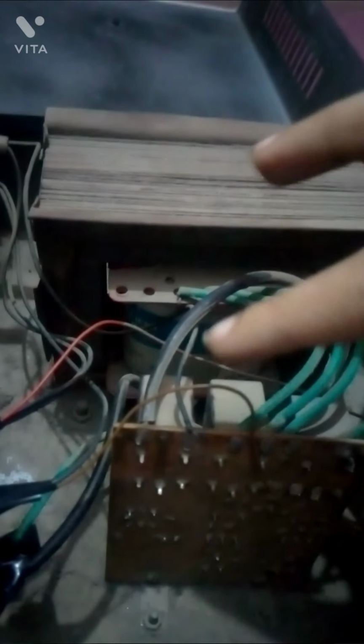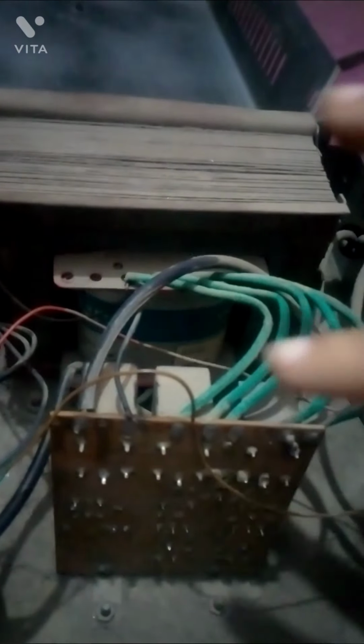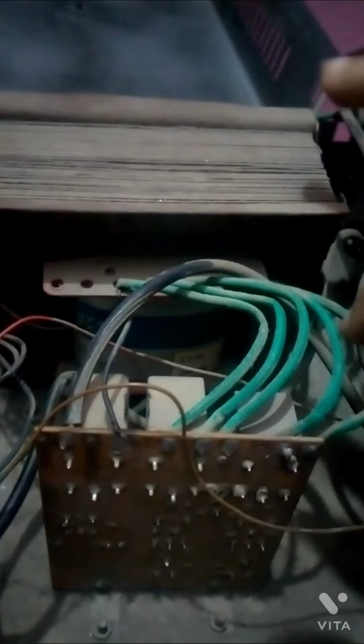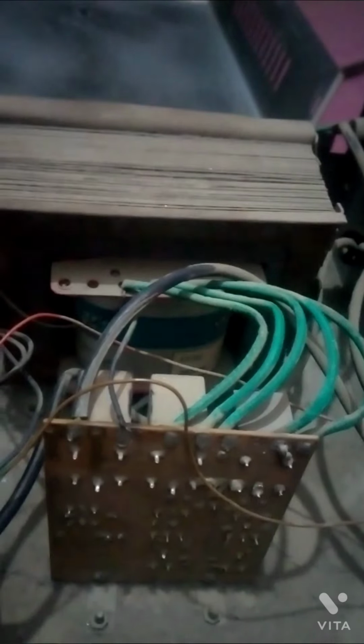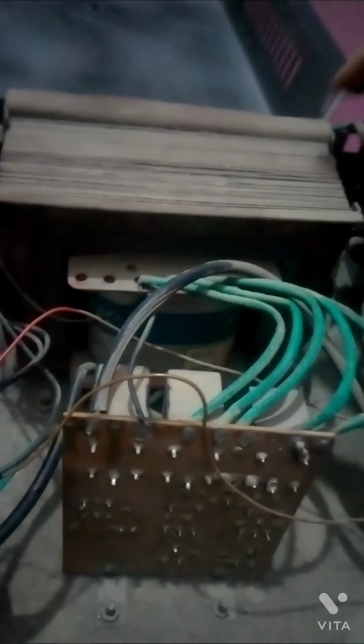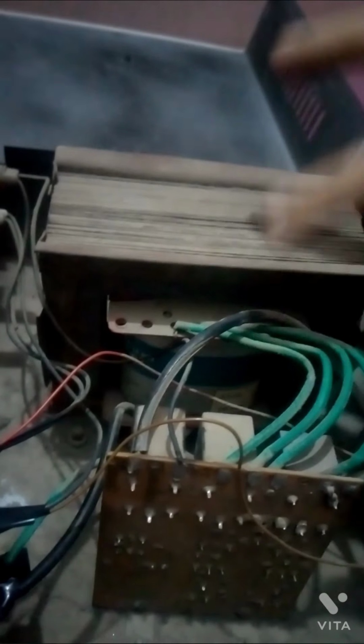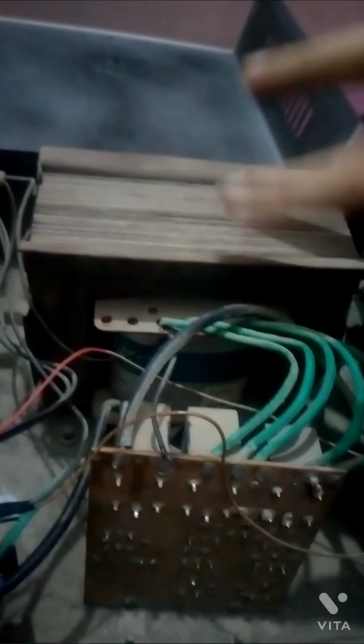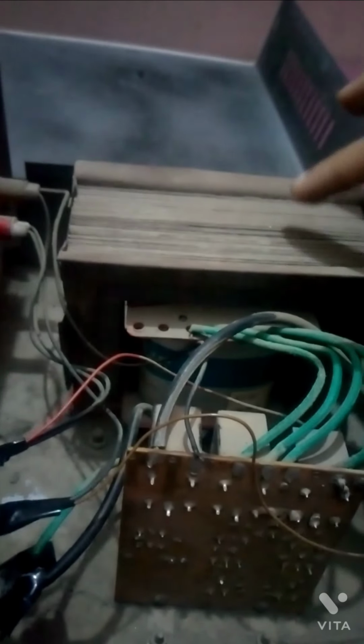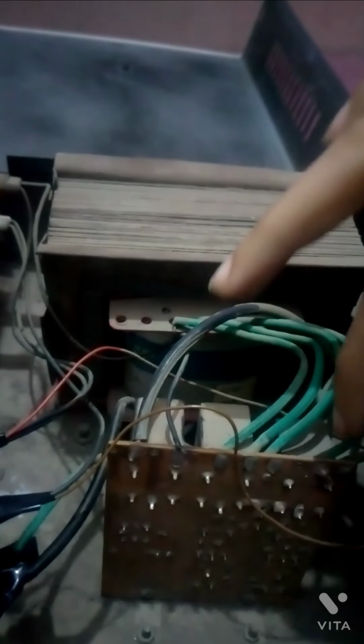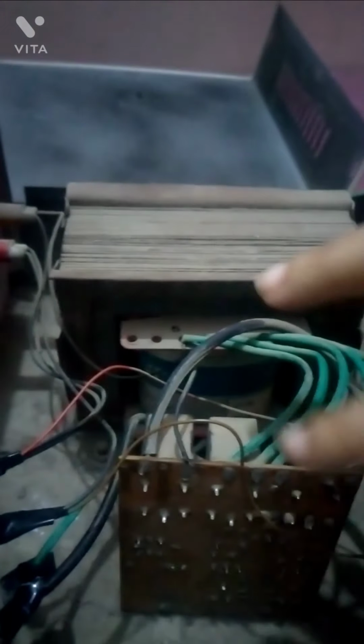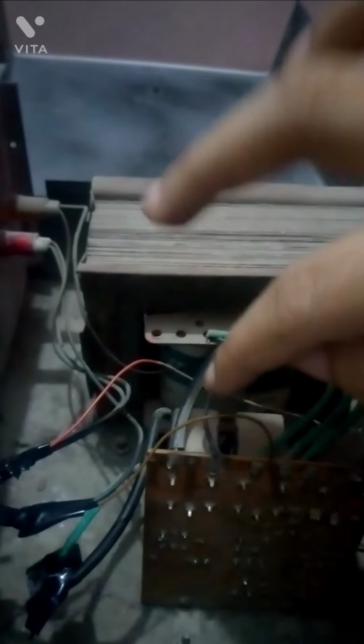The stabilizer takes the input, matches it with the feedback, which is AC, to detect how much voltage is present on the input line. Then it changes steps between neutral and first step, second step, third, fourth, and fifth, sending it to output. There is only one winding, the primary winding, which has 8 taps - one tap is common neutral, one is input phase, and the other 5 taps are connected to the output individually according to the voltage level. The star (control card) identifies the main input voltage using the feedback winding, determines the correct level, and controls the switching simultaneously.